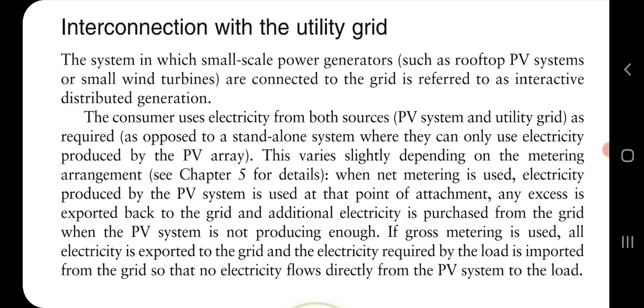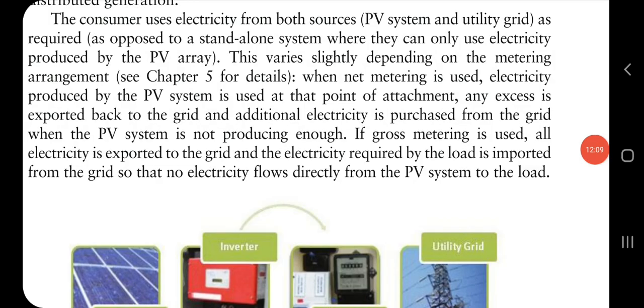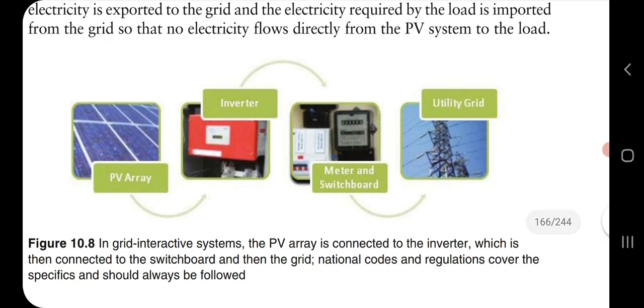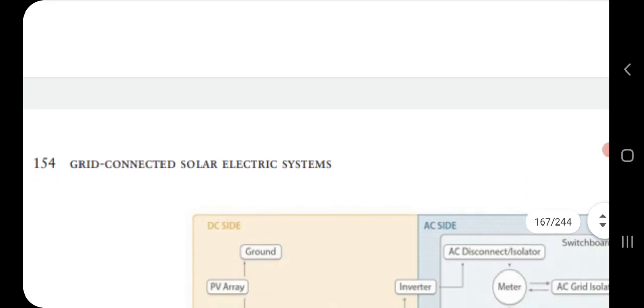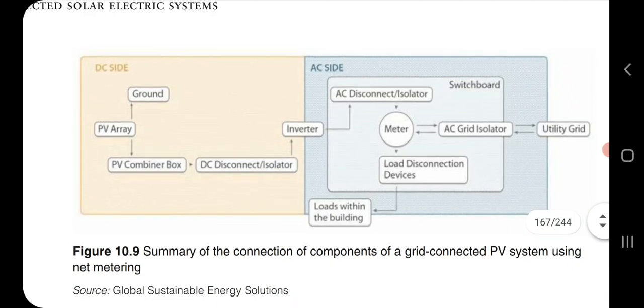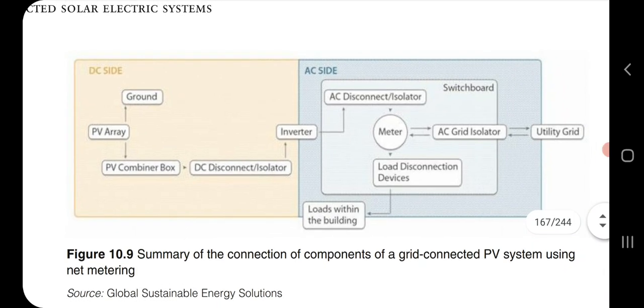In a gross meter, all electricity is exported to the grid, and electricity required by the load is imported from the grid, so that no current flows directly from the PV system to the load. This is how it works: from the PV array to the inverter, then from the inverter to the meters and switchboard, and then to the grid. Now they have shown a summary of the connection of the components of the grid-connected PV system using a net meter.